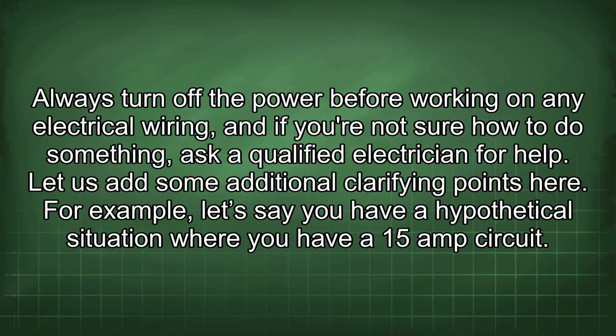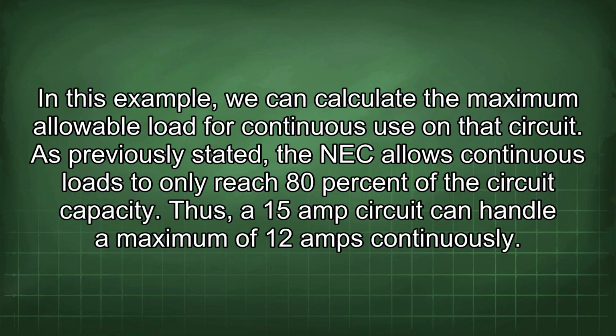Let us add some additional clarifying points here. For example, let's say you have a hypothetical situation where you have a 15 amp circuit. In this example, we can calculate the maximum allowable load for continuous use on that circuit. As previously stated, the NEC allows continuous loads to only reach 80% of the circuit capacity. Thus, a 15 amp circuit could handle a maximum of 12 amps continuously.